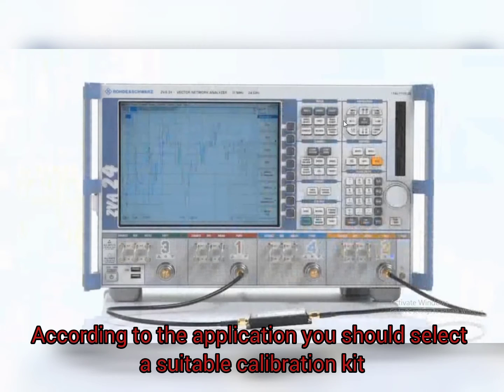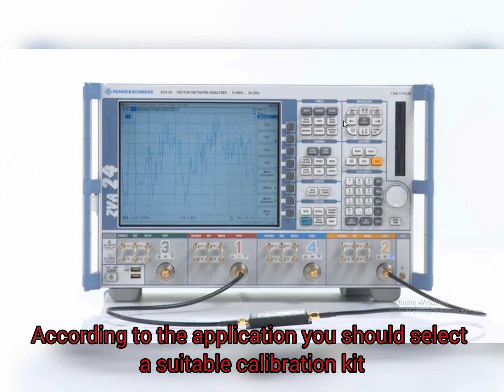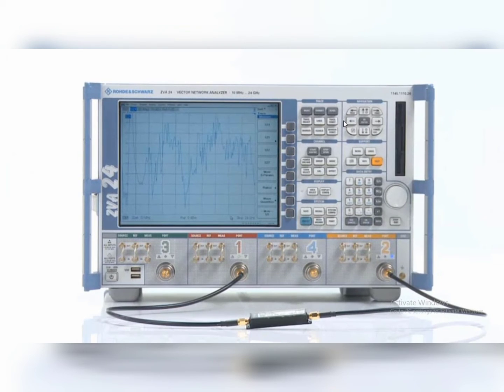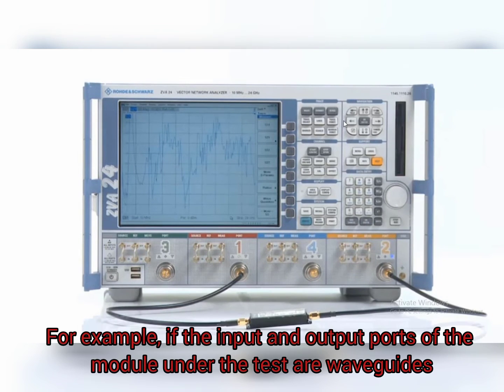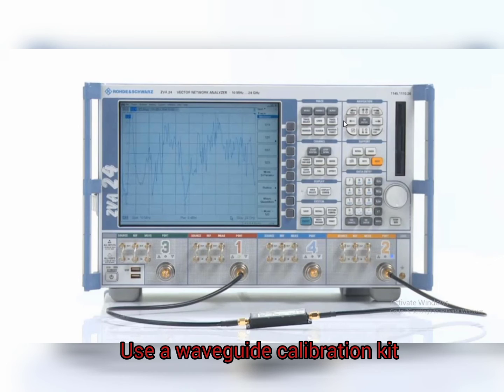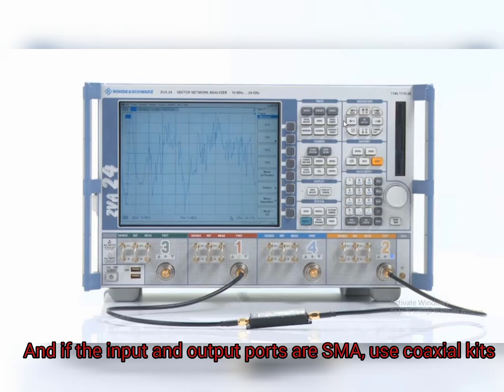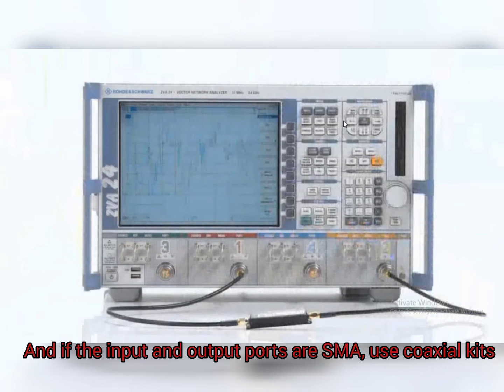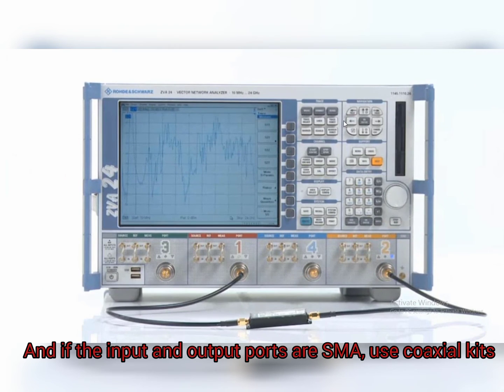According to the application, you should select a suitable calibration kit. For example, if the input and output ports of the module under test are waveguide, use a waveguide kit for calibration. And if the input and output ports are SMA, use a coaxial calibration kit.